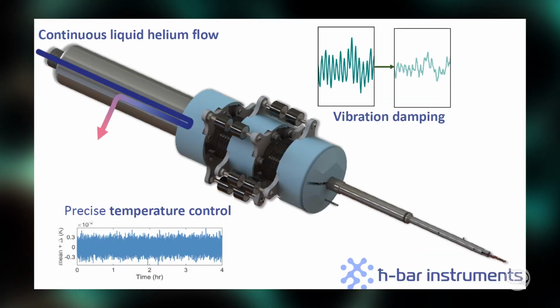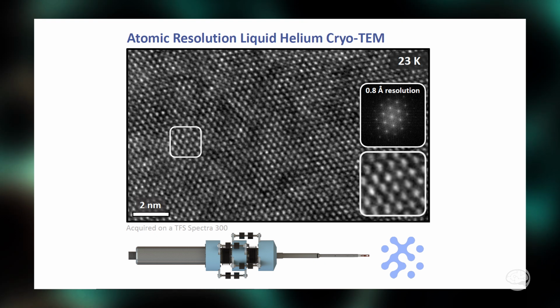Is there anything that stands out about this? There are a lot of cooling holders and cooling options out there, so what makes yours special? Unlike liquid nitrogen, which is easier to handle, liquid helium is a much more volatile cryogen, and that comes with problems like vibrations and limited hold times. So we've come up with a system that continuously flows helium into a heat exchanger, enabling cooling for long duration times. Unlike a typical holder, we have this module in the middle that dampens vibrations and reduces disturbances from that flow-in process. That would probably enable higher resolution images since there's less vibration, right?